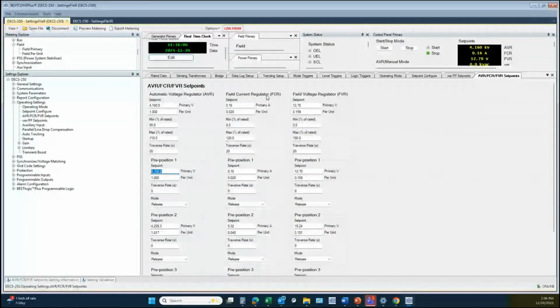Field current regulator, this is what, if you were to transition over to manual mode in the DECS 250, you're most likely going to go into FCR control mode. It regulates at a fixed field current level, regardless of what generator voltage is actually doing. This can be very useful for troubleshooting, and I often recommend starting the DECS when you're first commissioning a unit in FCR control, so that it doesn't worry about what the generator voltage is actually doing. And so if you have a sensing wire disconnected, it's not going to cause any issues if you're in FCR control mode.